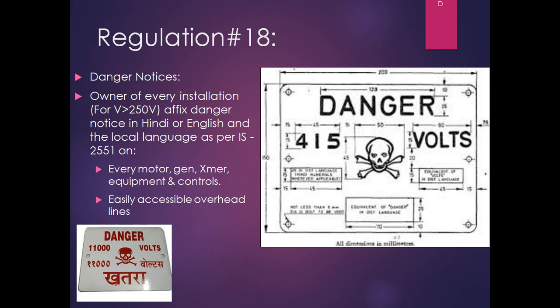And the relevant IS for this danger notice is IS 2551. Every motor, generator, transformer, equipment controls, they should have these danger notices. Also, the danger notices shall be affixed in front of easily accessible overhead lines. The language of the danger notice shall be Hindi or English and the local language, so that everybody can understand. Also, you can see it is a standard practice to write down the nominal voltage level on the danger notice.